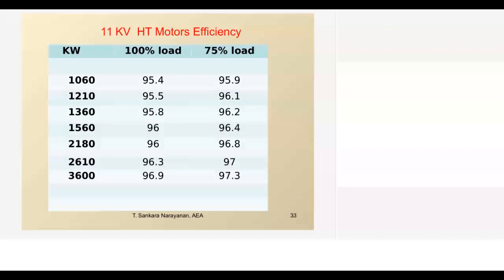So this is with respect to LT motors we have seen. As far as industry practice is concerned, up to 200 kilowatt they can manage with LT. Any load beyond 200 can be converted into an HT drive. So again, in an HT drive, the drop is not there. Motors are designed for 95 to 97% efficiency. So this is the advantage in an HT drive, 11 kV drive. Similarly, we have the same for 3.3 and 6.6. So predominantly, high tension motors have better efficiency compared to LT motors.